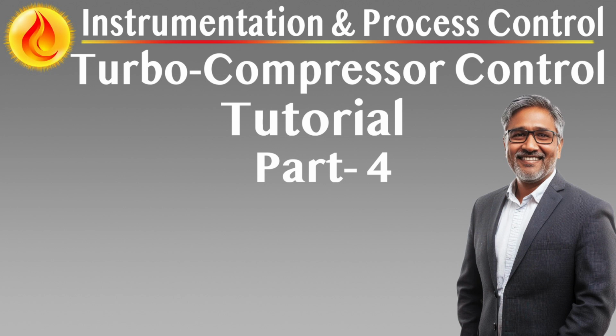This system provides early detection, local and remote annunciation, and automatic suppression activation to mitigate fire and gas incidents. All detection devices are hardwired to the skid edge junction boxes and interface with the external platform F&G system, which executes final shutdown actions and suppression logic. The TCCS acts as the interface and control enabler for detection, signaling, and interlock readiness.